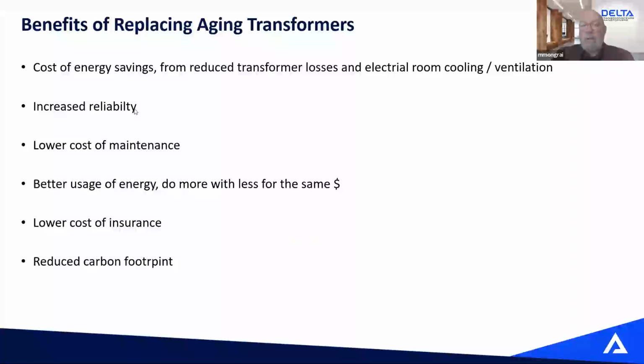You're going to have an increased reliability because instead of relying on an old transformer at the end of life that can fail at any moment, you have a brand new transformer that's fresh. Your cost of maintenance will be lowered. An older transformer will need more maintenance, will need more periodic checks to make sure it won't fail. You do a better usage of your energy because you do more with less for the same money. So that money that you used to spend on losses, now you can use to spend on other energy. The transformer consumes less. Your cost of insurance will lower because most of the time when you have an old aging transformer that shows signs of imminent failure, your insurance cost can go up. And you reduce the carbon footprint, which is one of the most important things we need to think about nowadays.